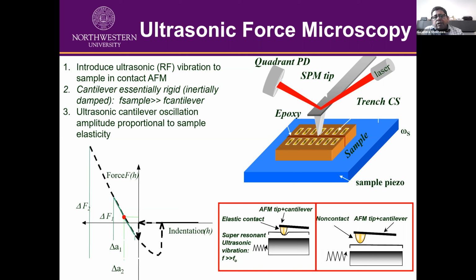So this technique came, ultrasonic force microscopy, where we oscillate the sample at a pretty high frequency. So you can create an out of plane vibration of the sample, and that indents the probe to a high contact force with elastic contact. So basically you can compress that part. And that technique allows you to measure the mechanical properties. Through force distance curves, you can extract the mechanical properties of the layers below that. How deep we can go, we haven't tried that much, but a few layers below the surface, you can do it.